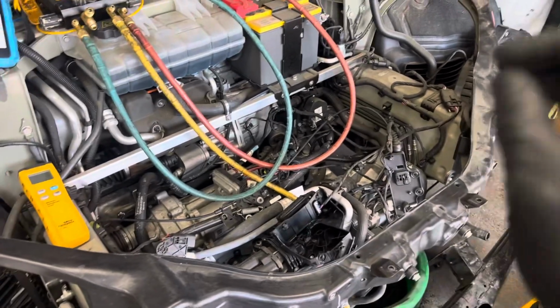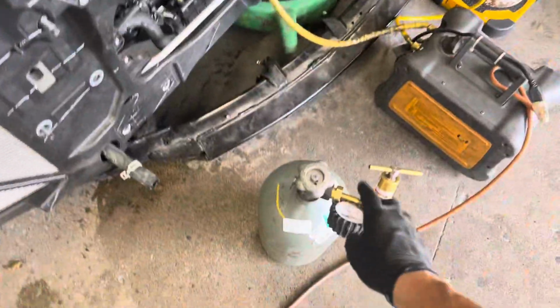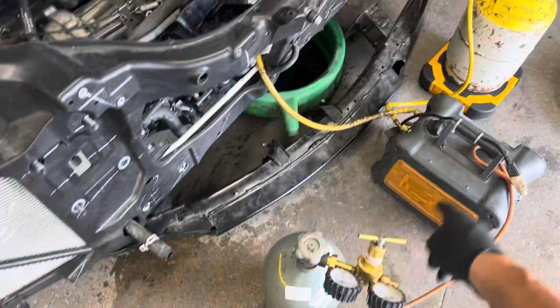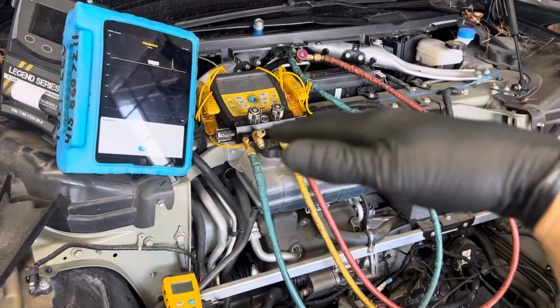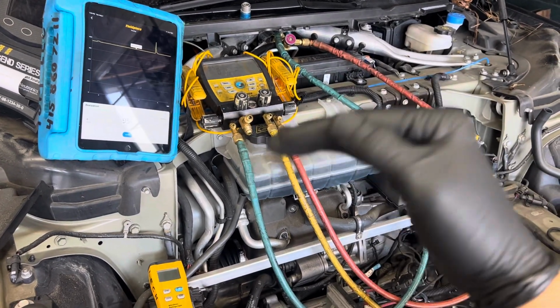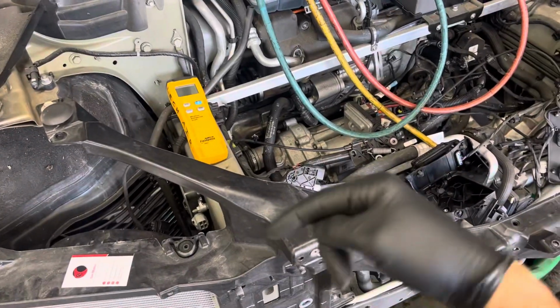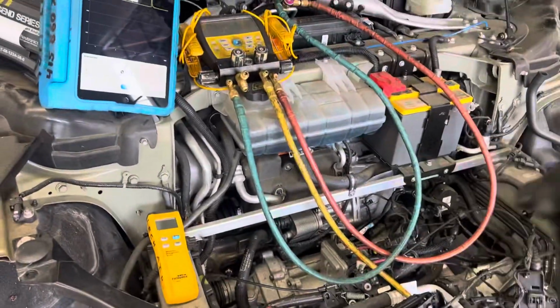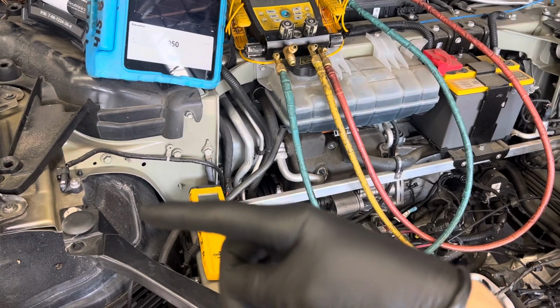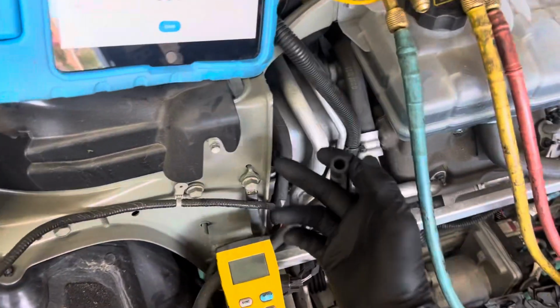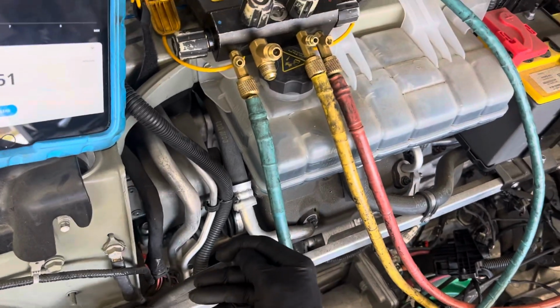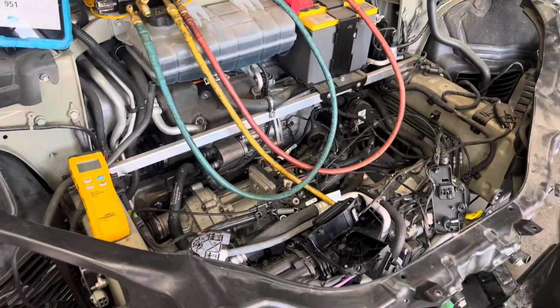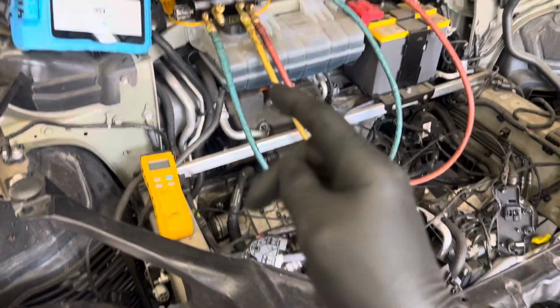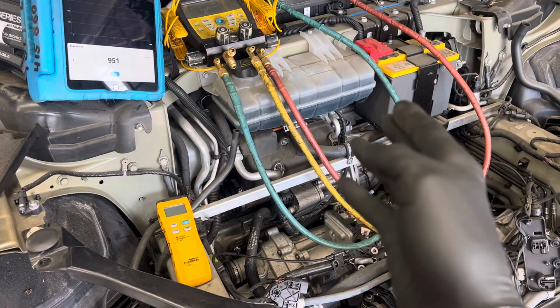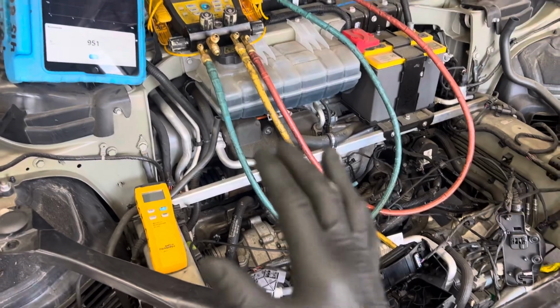You're not going to get that out. The new receiver dryer is not going to get that much water out. So that's where you break out the dry nitrogen. And now I'm going to purge dry nitrogen into the system to bring it up to roughly 0 to 1 or 2 psi, just positive atmospheric pressure. So when a technician opens up the line to remove and replace parts, no atmospheric air gets pushed in, and the technician takes their little rubber plugs and presses a little rubber plug onto the metal lines to plug them off and not let any atmospheric air inside the system to contaminate the ester oil that is highly hygroscopic.